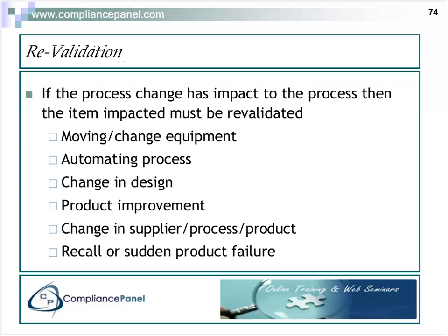So if we do move or change equipment, if we do automate a process that wasn't automated, if we change a design, if we make a product improvement, we change suppliers, process, or product, we have a recall or sudden product failure, all of those items need to drive us towards considering revalidation.